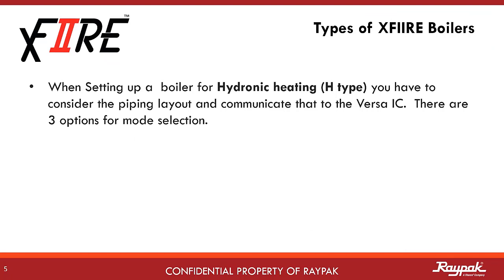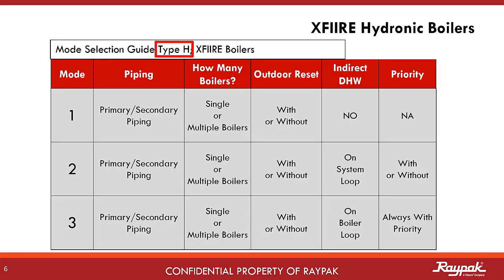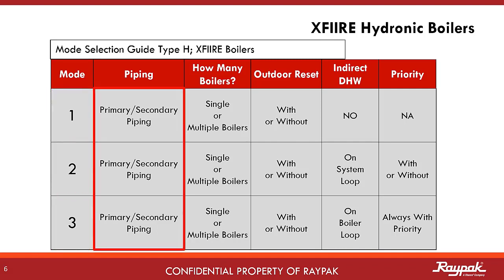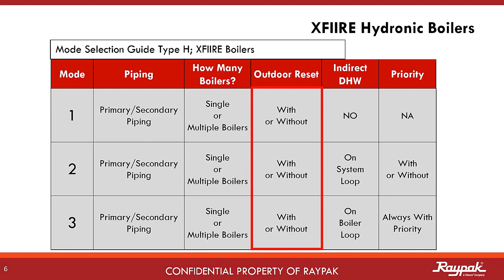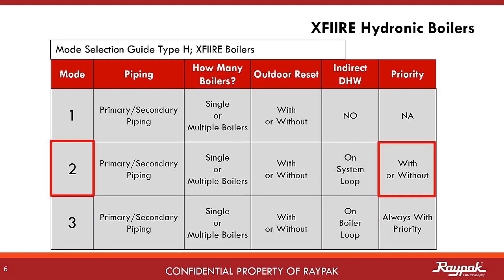When ordering a hydronic heater, there are three possible ways to set it up. These are called modes and are effectively operating programs for the boiler. If the appliance has a water heater ID card, then it is a water heater and there is only one mode of operation. For hydronic type boilers there are three modes — Mode 1, 2, and 3. All must be plumbed primary-secondary as the X-Fire boilers are low-mass. All three modes can be applied to single or multiple boilers and all can run with or without outdoor reset. If there is no indirect, then it is Mode 1. If there is an indirect system on the system loop, then it is Mode 2. If the indirect is on the boiler loop, then it is Mode 3. Mode 2 can be run with or without priority, while Mode 3 is always with priority.